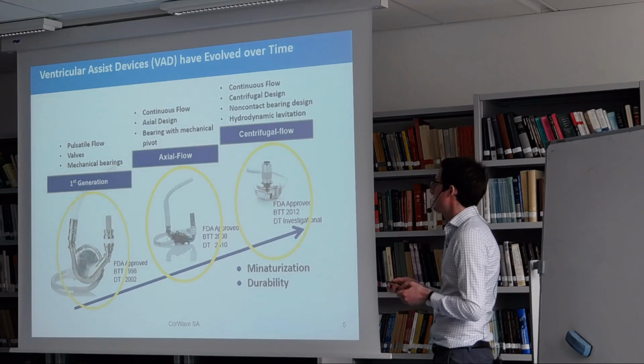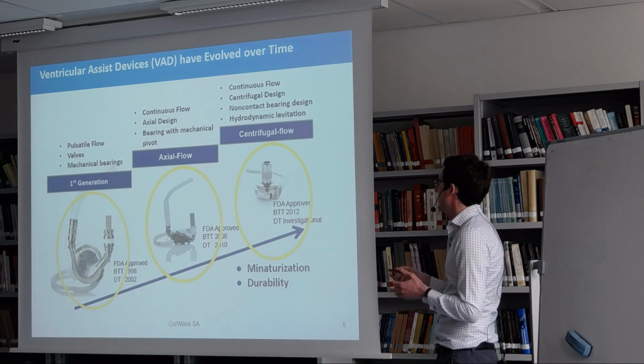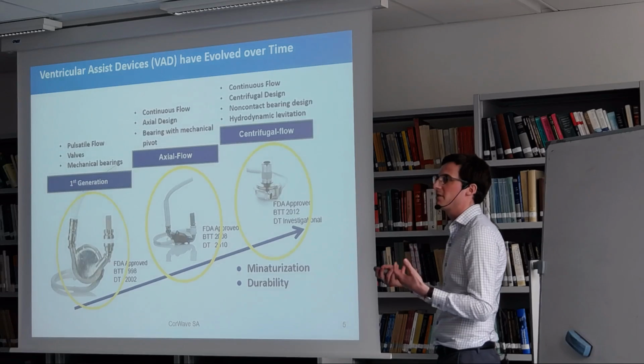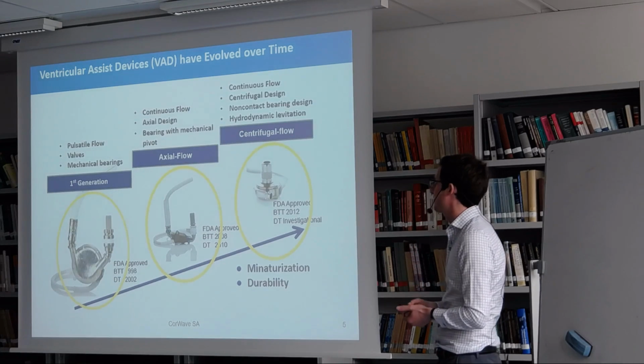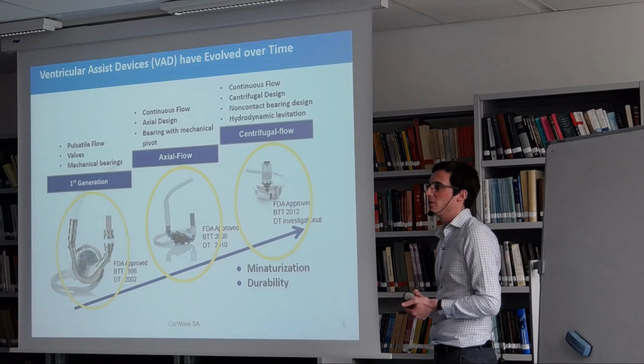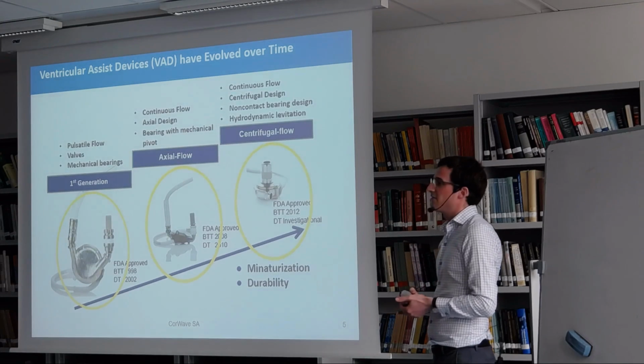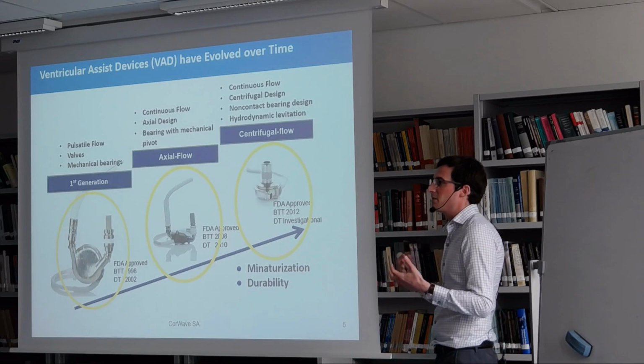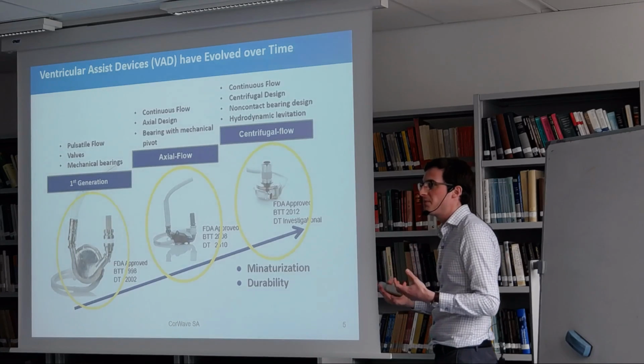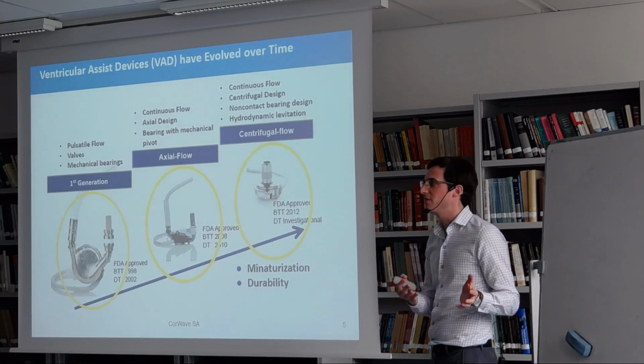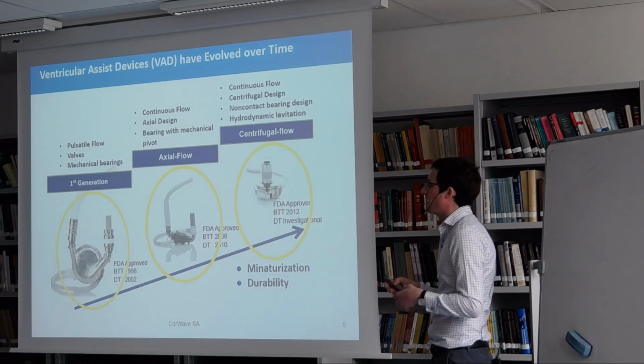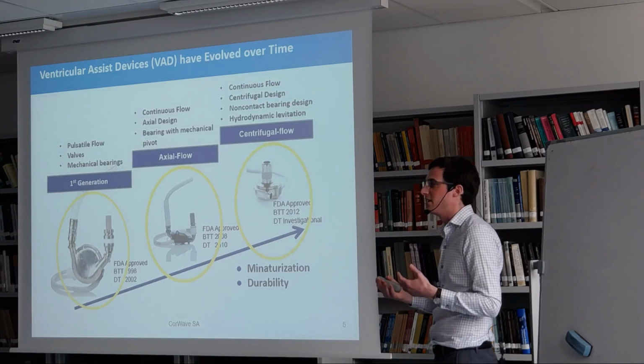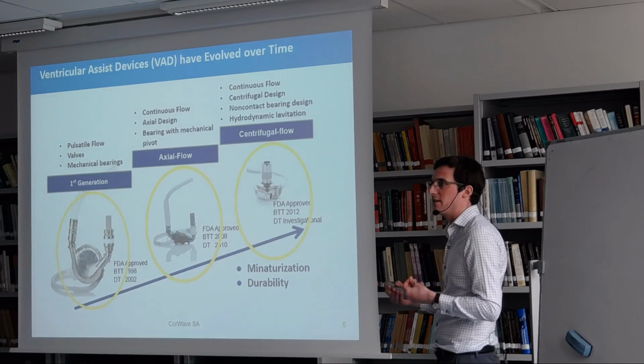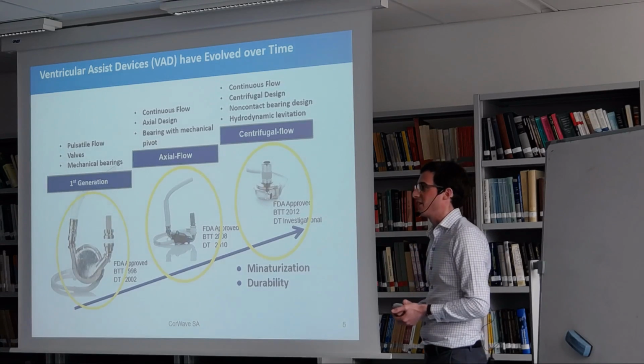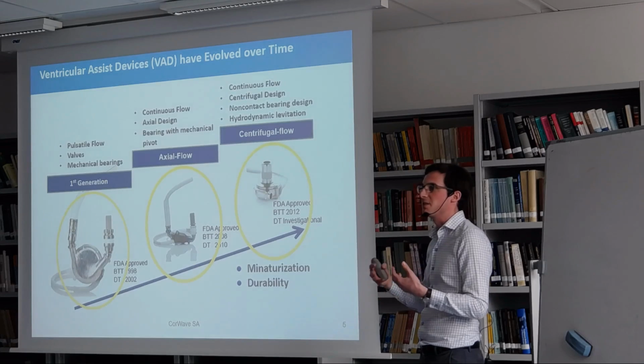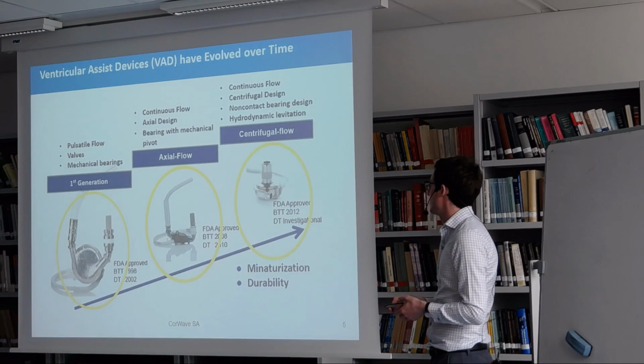And a bit later, but in a similar time frame, another type of device was developed, which are centrifugal flow devices, which are a bit smaller in size and which don't have any mechanical bearings. There was always the expectation, if you have a mechanical bearing in the pump, that the bearing will fail at one point because of the previous experience which was had. So these pumps have hydrodynamic levitation, magnetic levitation, to avoid the bearing and thus avoid some side effects which may be possible. And this is the promise of these devices which are currently entering the market.